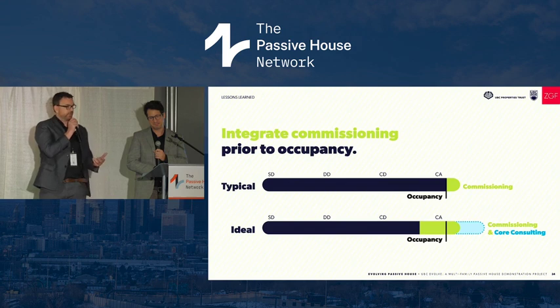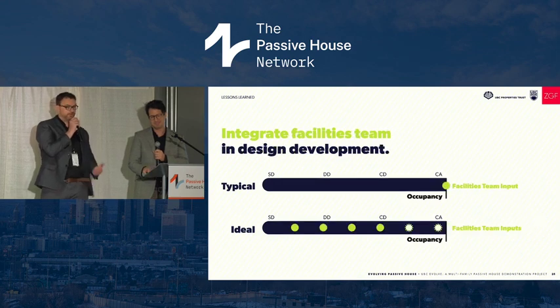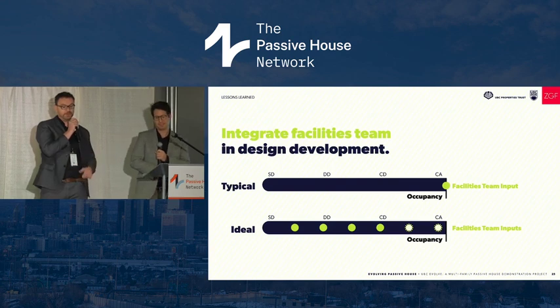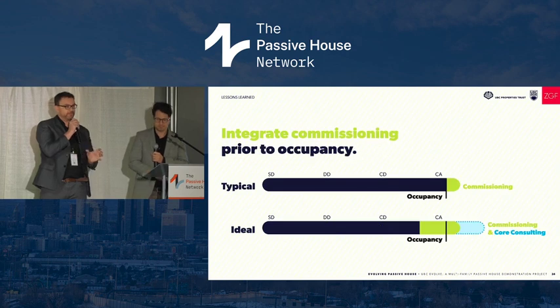The one real challenge here was with the semi-centralized HRVs. They had a factory setting that only allowed 50% of the air coming into the space. That caused a huge issue in the first 9 months, and it took a long time to find the source. Now we're looking at bringing the commissioning authority in earlier, and keeping the core consulting team on the project longer—meaning a time-and-materials response for post-occupancy, with the core consulting team helping problem-solve where the issues are.